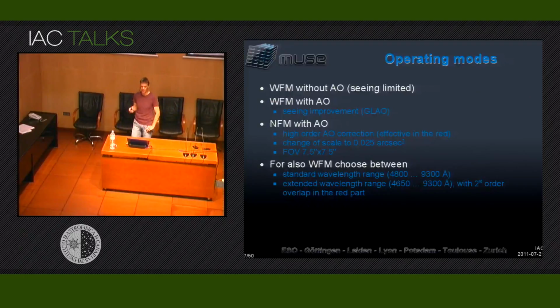There's not only the wide field mode in MUSE. It turned out early in the design that with just one small optical element, you can also change to a narrow field mode. The wide field mode you can of course also use without AO, because AO will not be available 100% of the time, just because atmospheric conditions are not right, or maybe because of technical problems. So you can do that without AO in seeing limited mode, and for the wide field mode you can have a moderate seeing improvement using ground layer adaptive optics.